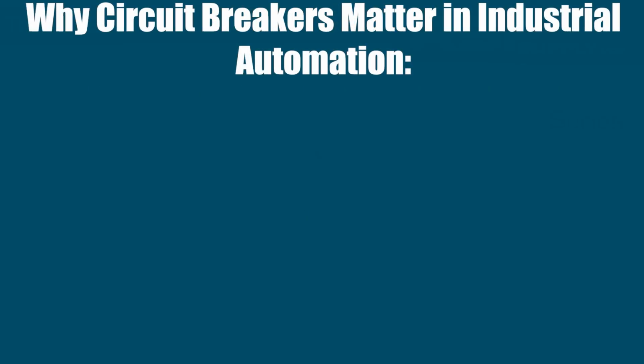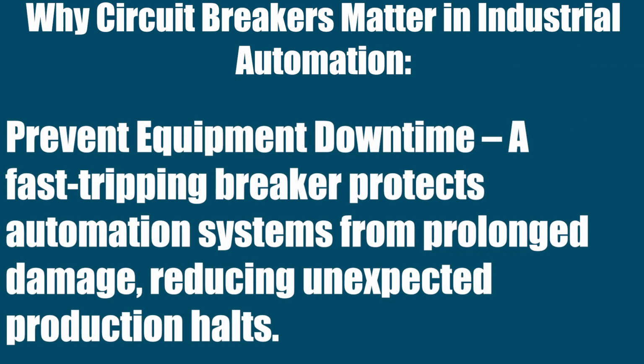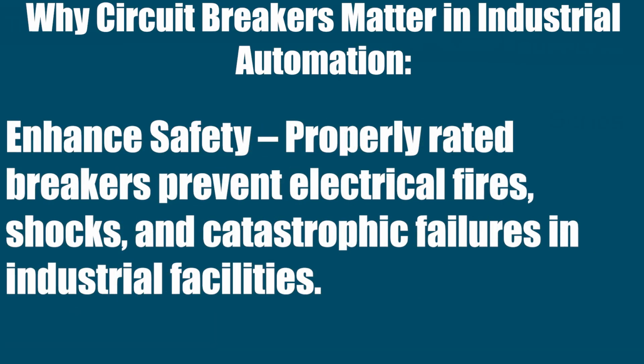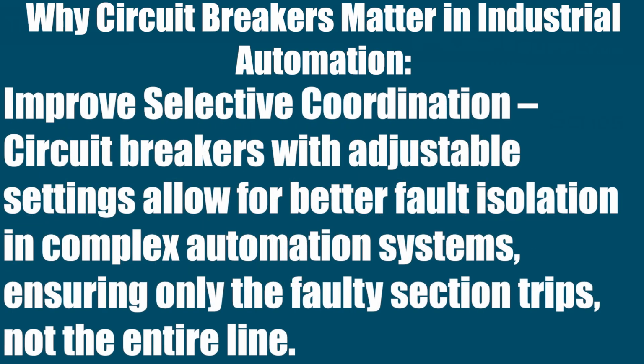Why circuit breakers matter in industrial automation. Overall, they prevent equipment downtime. A fast tripping breaker is going to protect automation systems from prolonged damage, and this reduces unexpected production halts. It also enhances safety. Properly rated breakers prevent electrical fires, shocks, and catastrophic failures in industrial facilities. There's improved selective coordination. Circuit breakers with adjustable settings allow for better fault isolation in complex automation systems. This allows only the faulty section to be tripped, not the entire line.